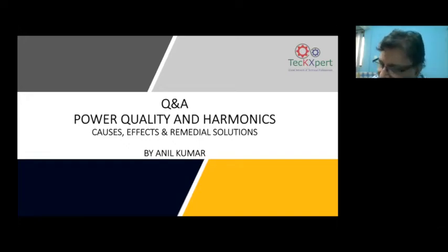I'm asking once again, are there any such rules for the harmonics? On the harmonics also, the CEA regulation is very clear that IEEE 519 should be followed for harmonic regulation. CEA has come out with all this regulation last year and they have sent it to all the state electricity boards to implement this. So it's a matter of time that this will come, and in the implementation, harmonic voltage should not go more than 8% at the coupling point, and harmonic current should not go more than 8 to 10% to 15% depending on the fault level at the point of coupling. And the power factor should be within 0.95 plus minus. So this is already there. Maybe it will come as a law in the coming times, I think.